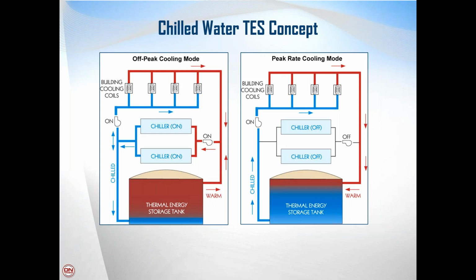So inside the tank, there are actually two bodies of water in that tank. They're not separated by anything other than the fact that the colder water, shown in blue here, is denser and is going to want to stay at the bottom of the tank, and the warm water at the top of the tank will stay at the top, and the two bodies of water will remain relatively isolated from each other and stratified within the tank.